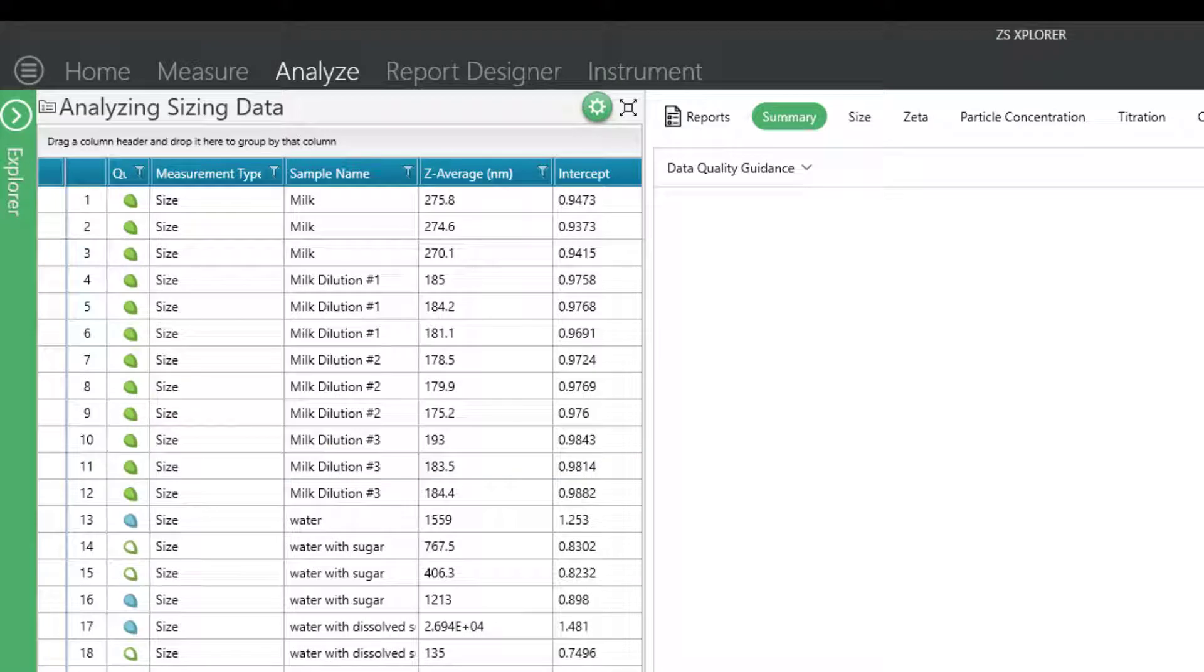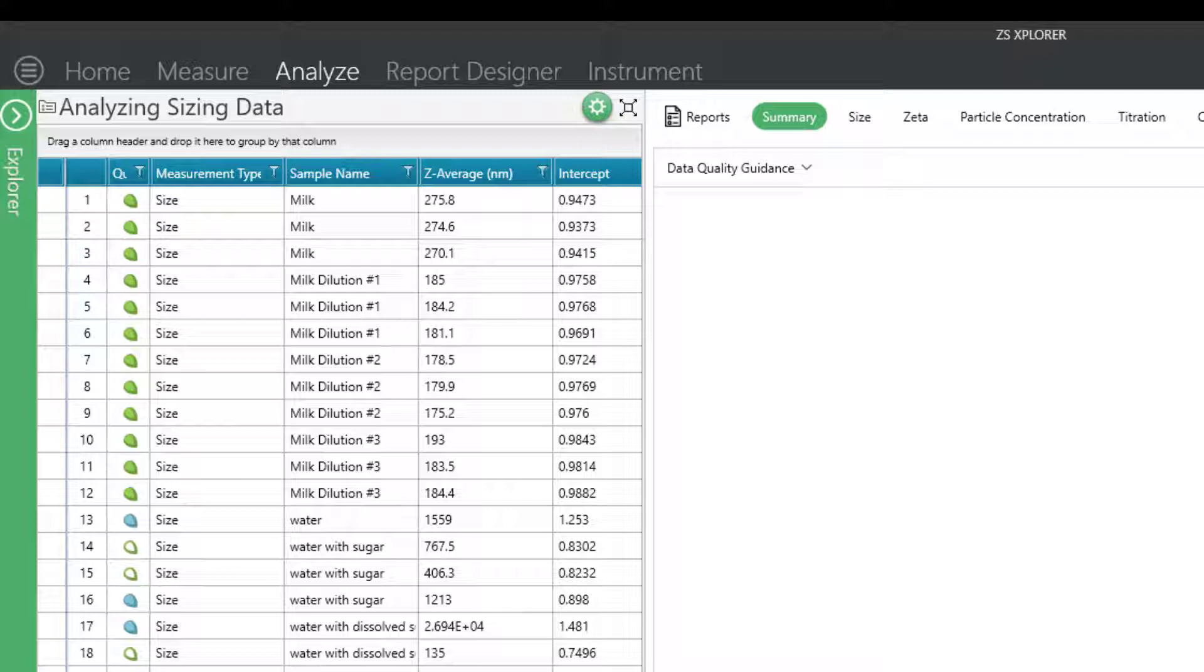One tip for analyzing samples for the first time is to do a small concentration study. Especially if your sample is particularly cloudy in nature, it's a great idea to do a few dilutions of the sample to determine the proper concentration range for accurate results.